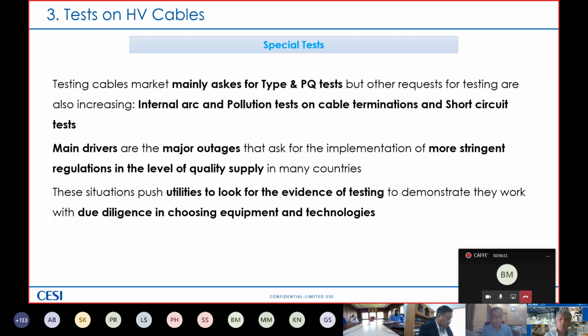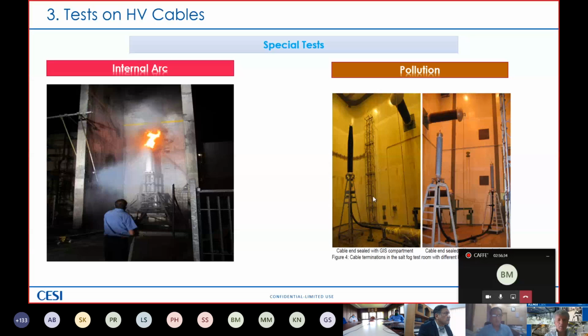The main drivers are the major outages that ask for the implementation of more stringent regulation in the level of quality of supply in many countries. This situation pushes utilities to look for evidence of testing to demonstrate they work with due diligence in choosing equipment and technologies. For example, let me talk about the picture on the left, internal arc. Here you can see the facility we have in Milan. This is one friend of mine during nighttime, because these tests are performed only during nighttime. I will tell you why in a while. He is trying to extinguish the fire that was caught on top of a cable termination.